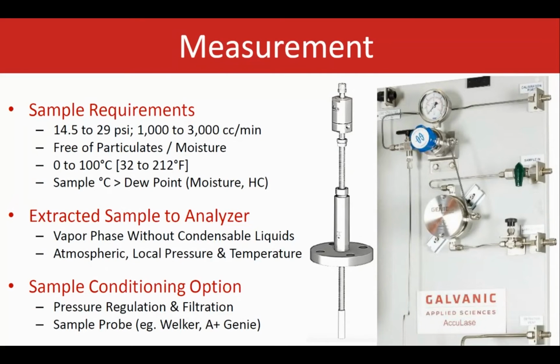Some information here regarding the sample, basically general requirements, I should call them, that include pressure, temperature, and dew point, as you can see all this information here. A sample conditioning system is an option with this analyzer to make sure a nice, dry, clean, particulate- and liquid-free sample goes to the analyzer. The sample conditioning system includes switching valves, pressure regulators, and a liquid membrane separator as the main components. There are other techniques, for example, using a Genie probe membrane that can be offered as well to insert the probe directly into the pipeline to separate the liquid and the particulates from the gas stream.